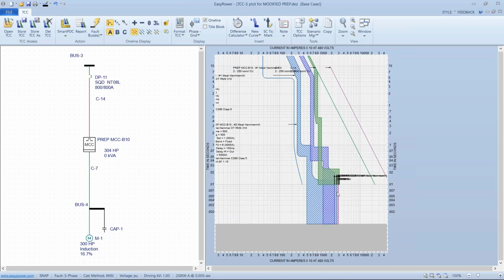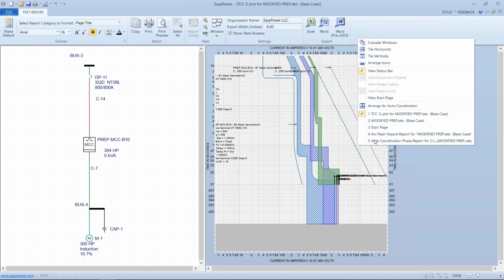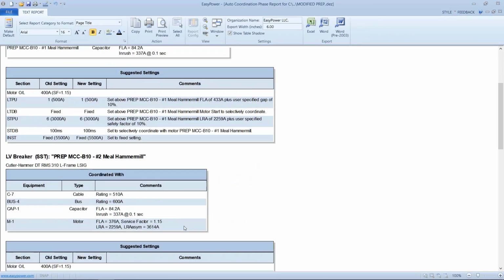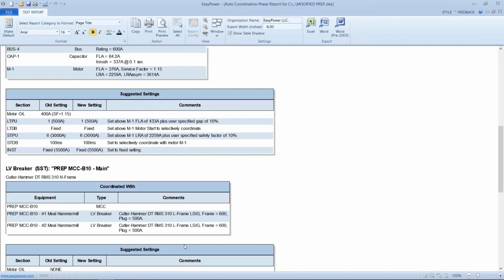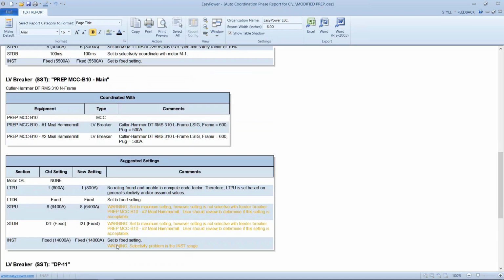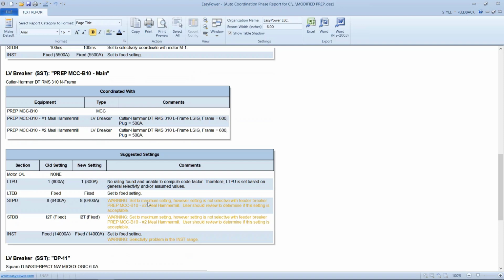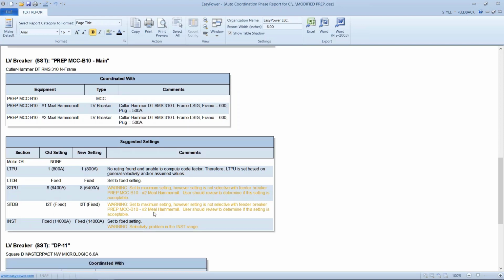The advantage of the tool, in fact, is that it's also easy to see how important Smart PDC can be in a case like this. As I invoke Smart PDC, it will give me a report of recommended settings and also the areas needing inspection.